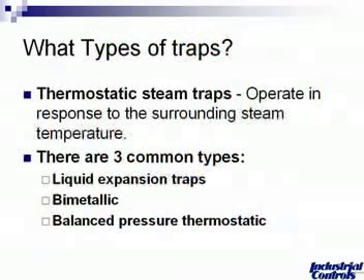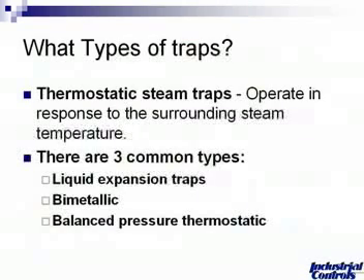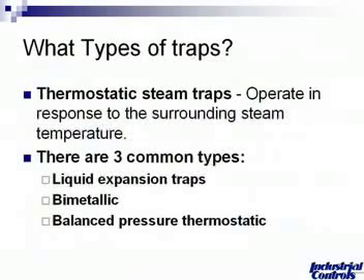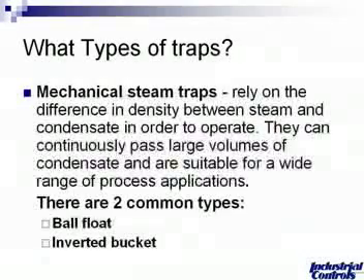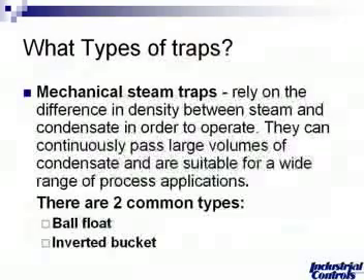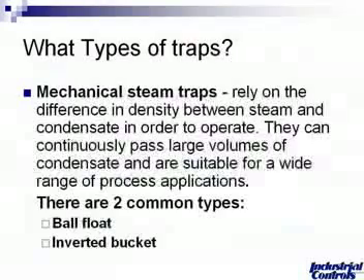There are several different styles of steam traps. One style is a thermostatic steam trap — they operate in response to surrounding steam temperature. In the thermostatic family there are three different kinds: a liquid expansion trap, a bimetallic style, and a balanced pressure thermostatic. In the mechanical steam trap family, mechanical steam traps rely on the difference in density between steam and condensate in order to operate. They can continuously pass large volumes of condensate and are suitable for a wide range of process applications. There are two common types: a ball float and an inverted bucket.